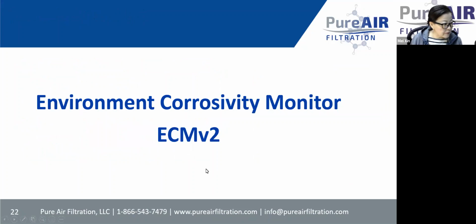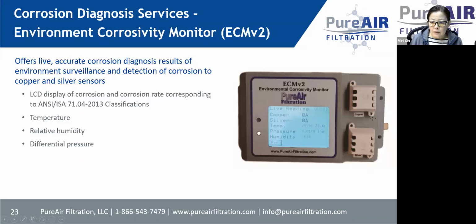Next, I want to go over our environmental corrosivity monitor, ECM version 2. For the corrosivity test kit, you have to put the kit for 30 days in the area where you may have concern and send it to the lab, which may take another 1 or 2 weeks to analyze and get results.